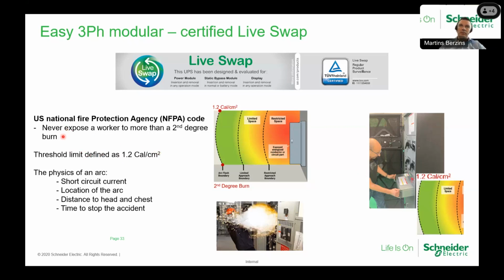So this is why we don't keep the hot swap naming. We changed it to live swap, because the hot swap naming does not have this 1.2 calorie per square centimeter notation. The live swap feature we have certified with TUV, which is a third-party European certification company that takes our UPS. They simulate this arc flash, and they test it, and they approve that yes, the UPS power modules, static bypass module, and display are live swappable. So that's why we have a live swap feature.